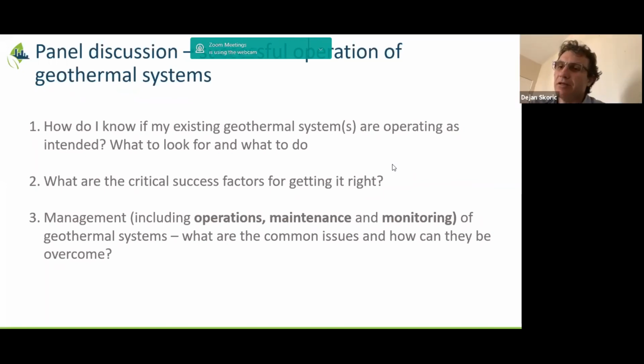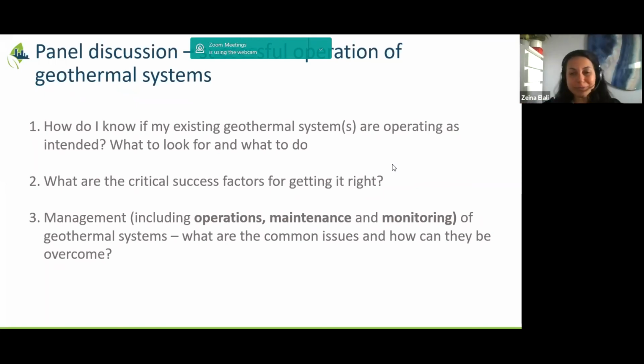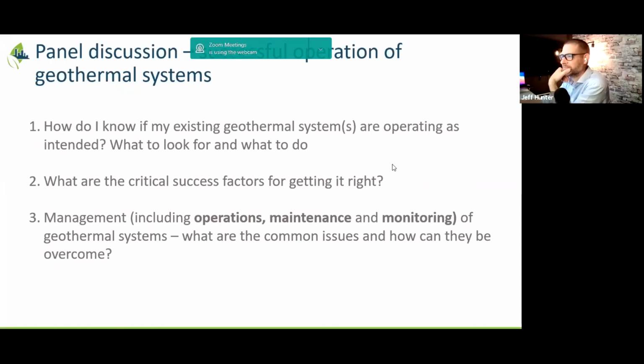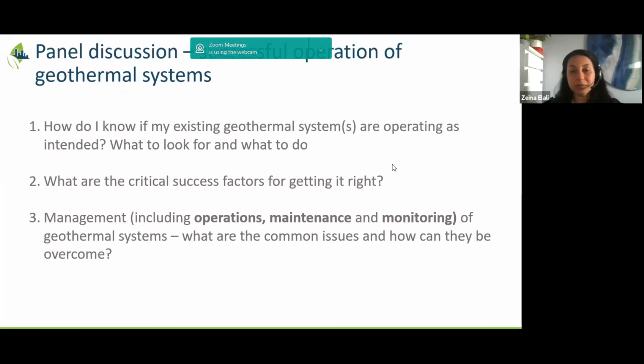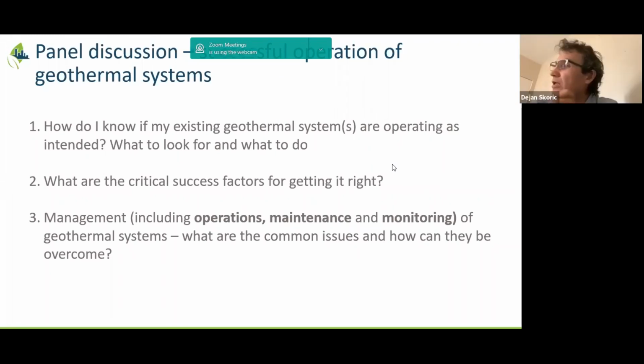R134A, looking at my list, has a global warming potential of 1,430 - it's quite big. So there's definitely importance in discussing refrigerants as part of the conversation when looking at the geothermal system and having your design team address that. The ones we've seen over the last year that Sean mentioned now have a global warming potential around 600, so maybe a third of what the standard was a few years ago. But it's not ammonia or CO2, which have extremely low potential.